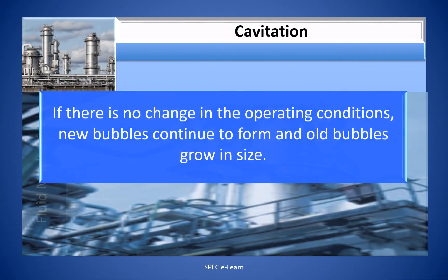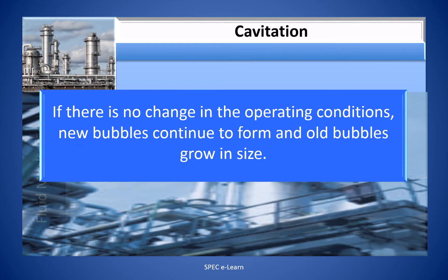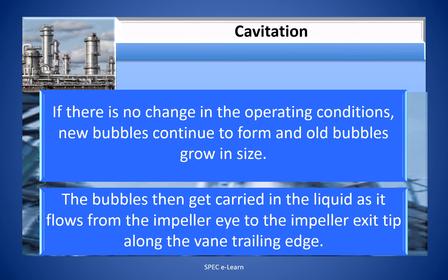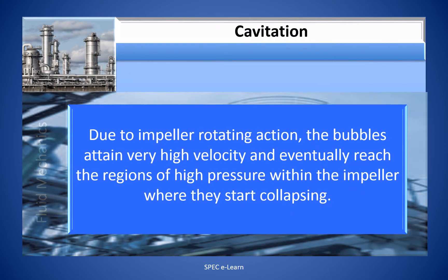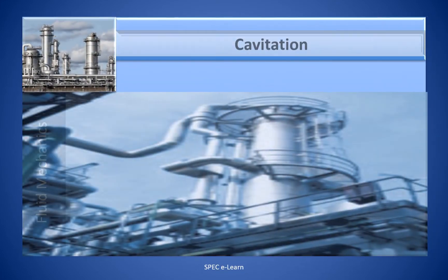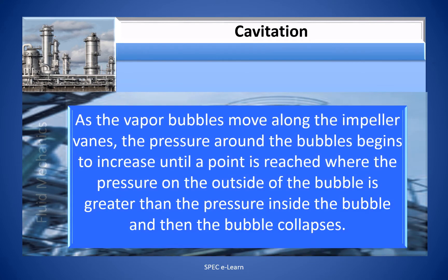If there is no change in operating conditions, new bubbles continue to form and old bubbles grow in size. The bubbles then get carried in the liquid as it flows from the impeller eye to the impeller exit tip along the vane trailing edge. Due to the impeller rotation, the bubbles attain very high velocity and eventually reach regions of high pressure within the impeller where they start collapsing. As the vapor bubbles move along the impeller vanes, the pressure around them increases until the pressure on the outside of the bubble is greater than the pressure inside — then the bubble collapses.